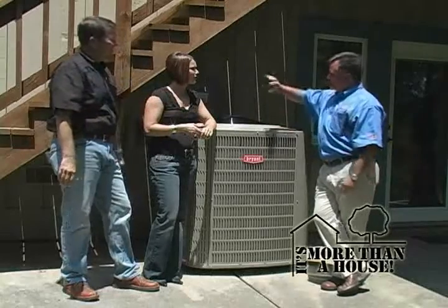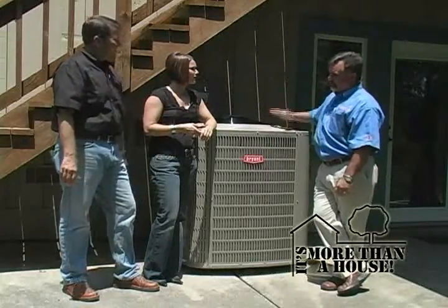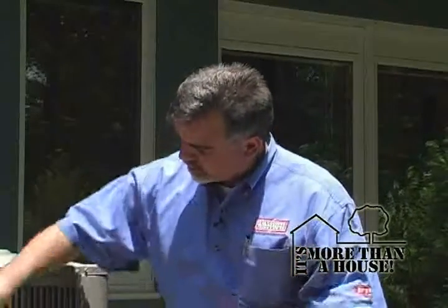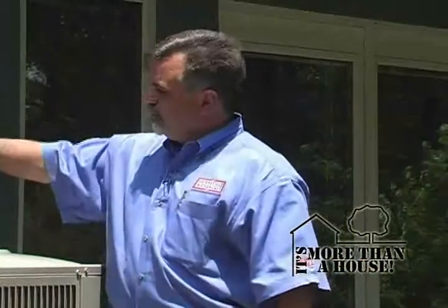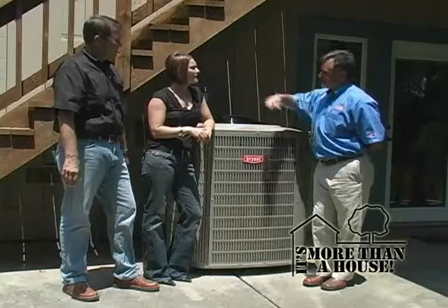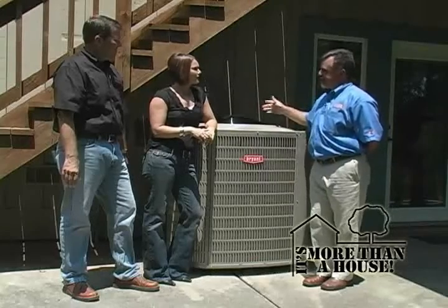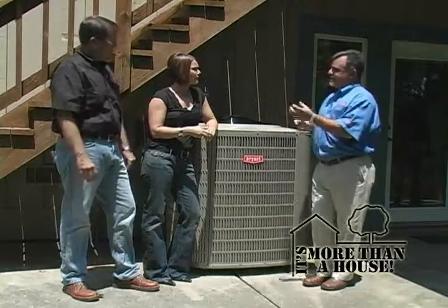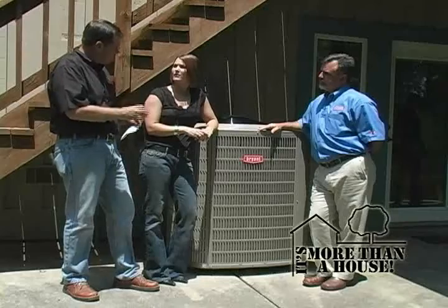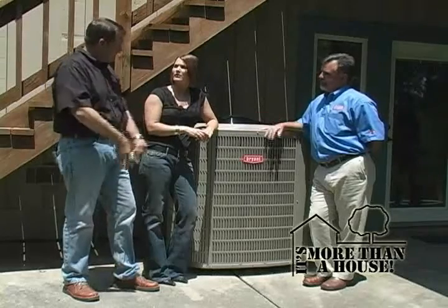It's really taking the heat out of the air, leaving cold air. It warms up the refrigerant, and that refrigerant carries the heat back into this unit here. The compressor compresses that vapor back to a liquid, pumps it through this coil, and this fan sucks air across the coil. You feel the heat blowing out the top of the unit — that's the heat coming out of the house. The refrigerant goes from liquid to vapor and back to liquid. That's why they call it a refrigeration cycle.